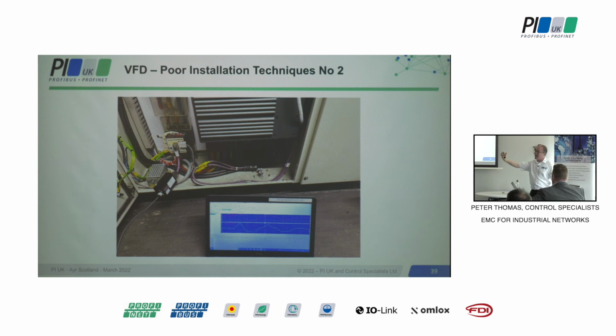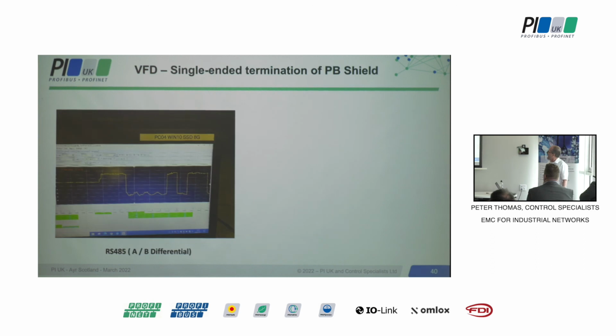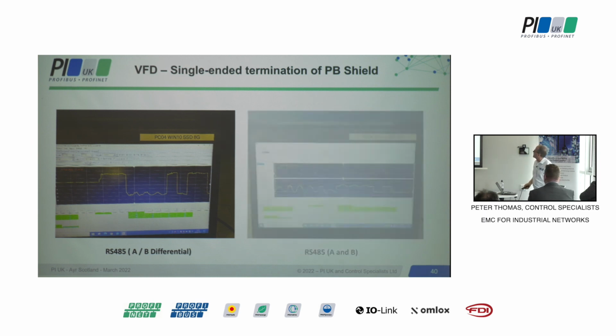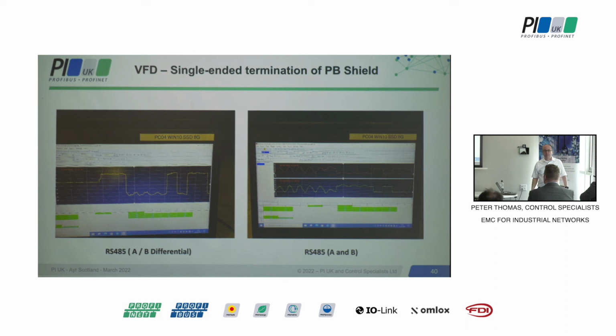So it's coming through the SIMOCODE onto the network, primarily because of all this poor cable segregation, and then multiply that by about 10 of them because they've got them all over the place. And then a couple of others on here. You can see there, this was a warehouse. They called me in during the pandemic, basically saying they weren't very happy with the installation. They wouldn't let me on site, so I sent them some gear down. They improved it. They had said they had only grounded at one end, but they asked me when I went down, would I check another one that they hadn't yet done? And that's the one that they hadn't done.